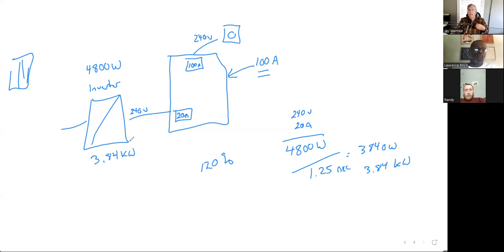The biggest inverter I could put here is a 3.84 KW inverter under this scenario. If you look online, manufacturers make a 3.8 KW inverter and a 7.6 KW inverter. Once you figure out that with a 100 amp service and panel, I need 3.84 KW, they just make that. The other most common scenario is a 200 amp service and panel, which would use a 7.6 KW inverter. Manufacturers have designed their systems to meet these common scenarios.